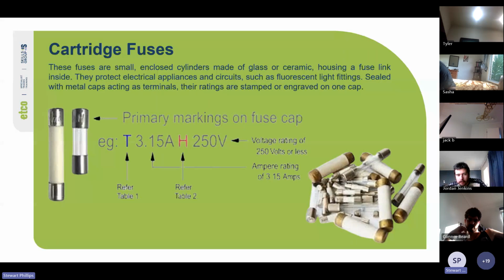So you've got the primary markings on the fuse cap. You've got T 3.15A H 250 volts. T means it's a slow blow. 3.15A means it's rated at 3.15 amps. I cannot remember what H stands for, and it's a voltage rating of 250 volts or less.